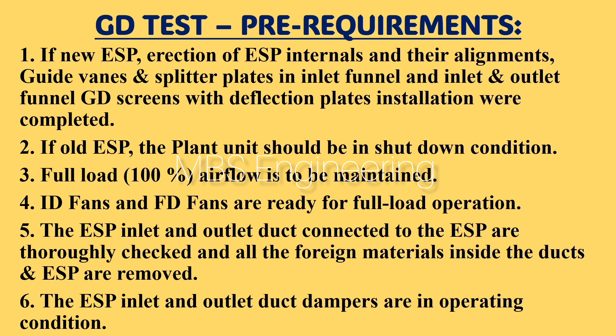Point 3: full load (100%) air flow is to be maintained. Point 4: ID fans and FD fans are ready for full load operation. Point 5: the ESP inlet and outlet ducts connected to the ESP are thoroughly checked and all foreign materials inside the ducts and ESP are removed. Point 6: the ESP inlet and outlet duct dampers are in operating condition.